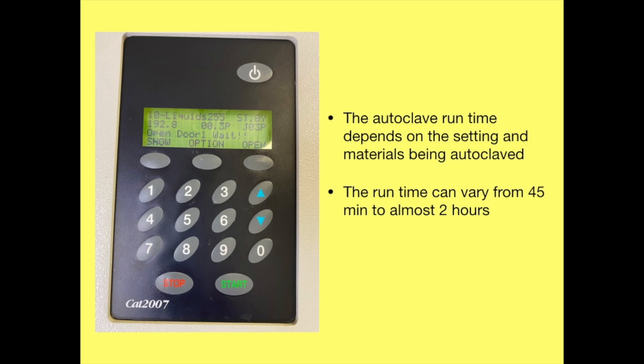The autoclave runtime depends on the setting and the materials being autoclaved. It can vary anywhere from 45 minutes to almost 2 hours. Once the run is complete, the display will read ready, and one can hit open. Allow a couple of minutes for the pressure seal to release and for steam to be released from the autoclave.